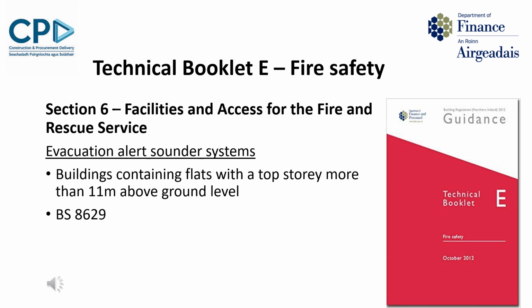A new requirement for the provision of evacuation alert sounder systems in buildings containing flats with a story more than 11 metres above ground level has been introduced in TBE. Although rare, there may be occasion for a fire and rescue service incident commander to order the partial or full evacuation of a building in the event of a fire or other emergency. Provision of these evacuation alert sounder systems will assist the fire and rescue service to evacuate these types of mid to high-rise residential buildings. It's felt blocks of flats with a top story lower than 11 metres can be evacuated by the fire and rescue service personnel simply by knocking on doors.